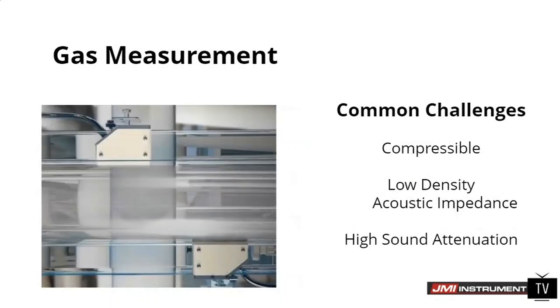So the challenges that we face with gas to measure standard volume flow is the compressibility and the low density of the gas. Compressibility has to do with standard volume flow. That's how much the gas will compress with pressure applied. So that is something that we need to get an accurate standard volume flow measurement, or normalized volume flow. And then low density gas, we talked about this already, but this has to do with the amount of signal that we can get through the pipe.